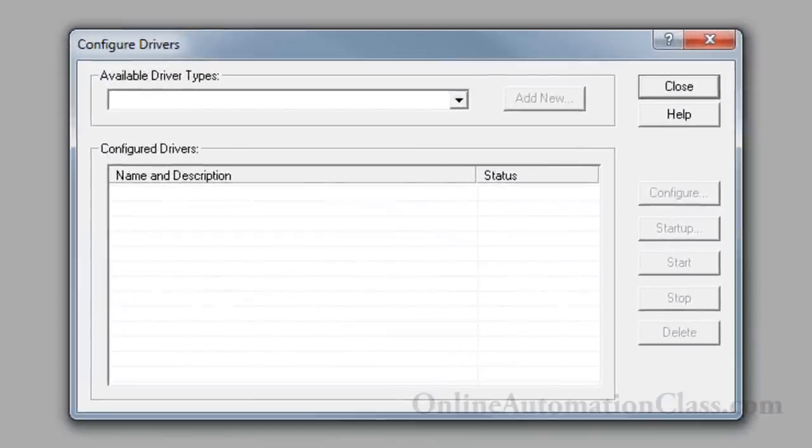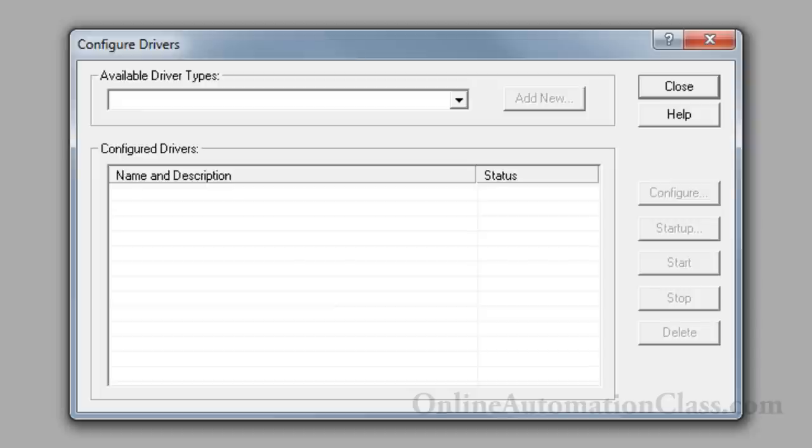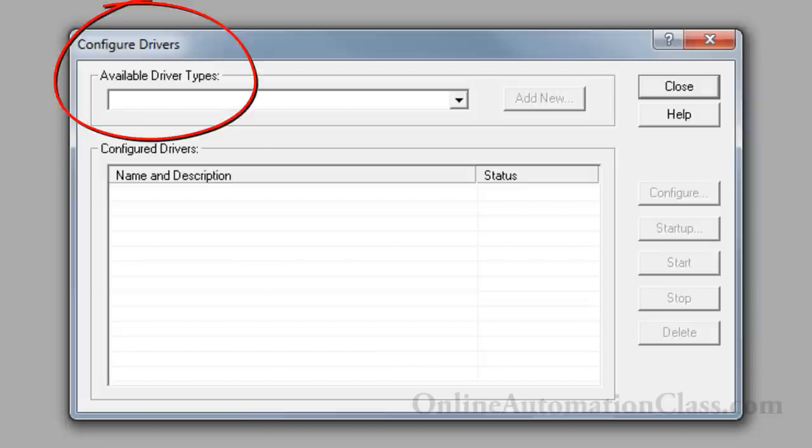In RSLinx, a driver is a communication protocol. Since the 1747L531 processor communication port uses a DF-1 communication protocol, click the available driver types drop-down list and select RS-232 DF-1 devices.